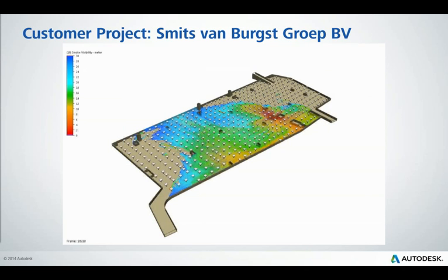Yeah, John, it's really cool when you look at these results, how the air rushing in through the hallways does a really good job to at least maintain a pretty open end effect, so that if people at least get to the ends of the car park, you can at least find the entrance and get out. So that, I find that really interesting, how well that really controls the smoke and keeps it essentially located. Yeah, that's a good point.